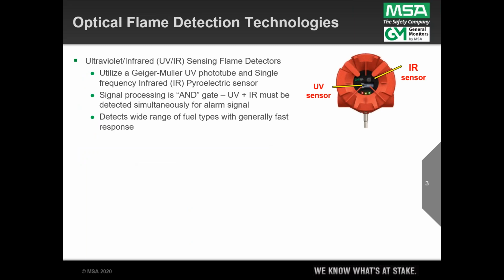So, optical flame detection technologies. The first sensor out there was an ultraviolet flame detector, rolled out in the 60s, and it actually saw a fire quite well. The problem was it also saw welding and lightning and all kinds of non-fire radiation sources. So our engineers coupled the Geiger-Müller UV photo tube along with a single frequency infrared sensor in the same electronic package. By using a basic microprocessor running AND gate signal processing logic, where the UV energy was of a sufficient level, and the infrared, which is part of a hydrocarbon fire emission signature, was present simultaneously within the field of view, this detector really augmented the false alarm rejection capability of that UV detector.